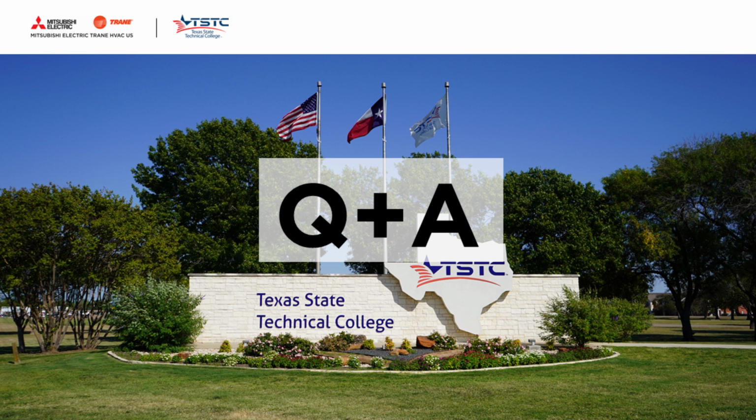Sure, Jay, I can add one more flavor to that. There are two functions that can happen at the same time. With more conventional HVAC systems, it was very difficult to offer different zones of the same building a truly independent set point. Because of how VRF functions, with each indoor unit only requiring the refrigerant that it is calling for, you really are able to offer your occupants independent set points, and those set points are not going to greatly impact the resulting energy cost. So that's the first idea: previously you weren't able to do that, now you can.